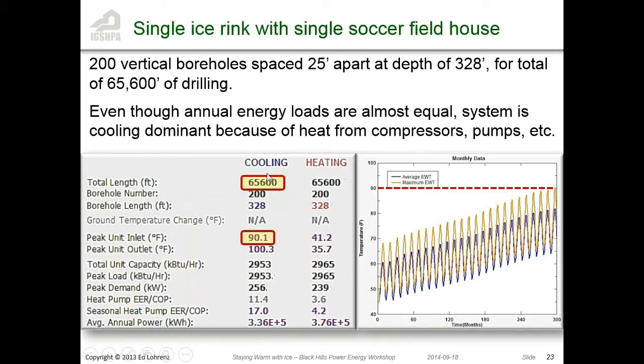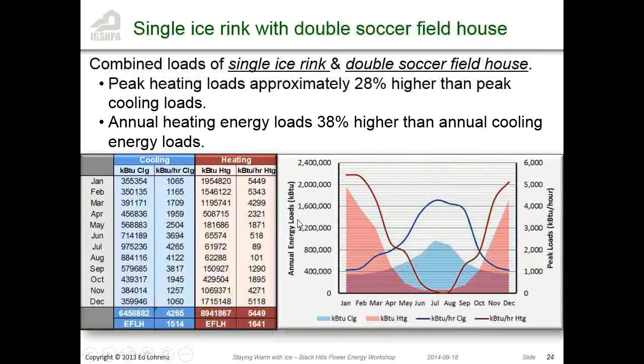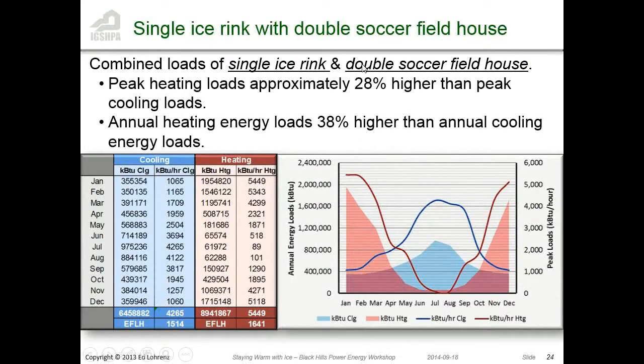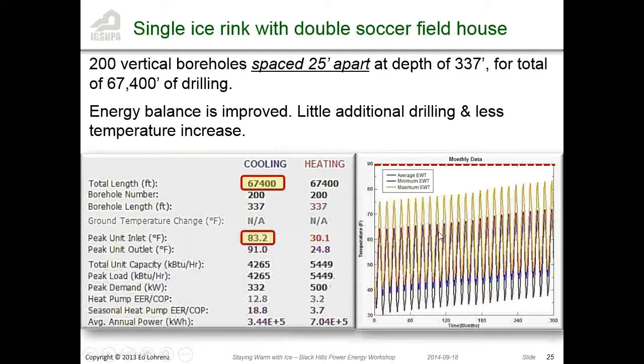And then single sheet of ice with a double soccer field house, all of a sudden our heating loads are a lot higher, and our peak loads as well as the energy loads. Now we've got a bit of a balance. Gives you some idea of how much heating you can do, taking heat out of the ice.